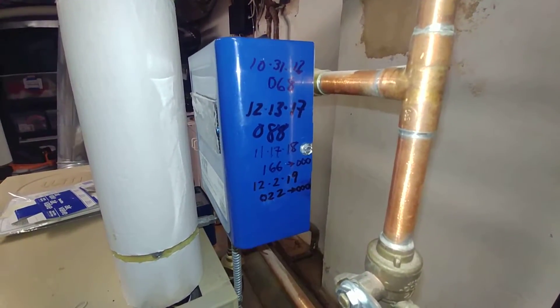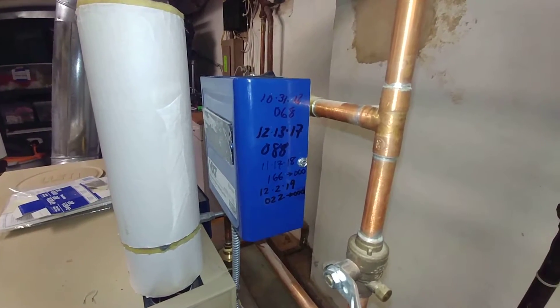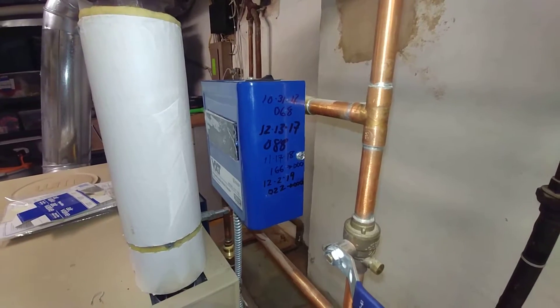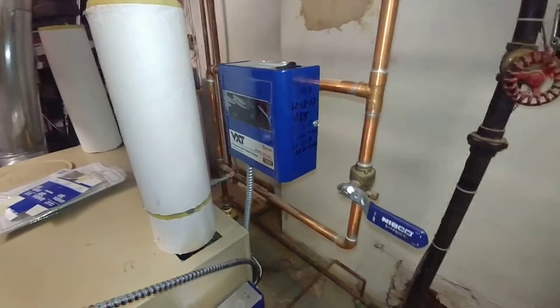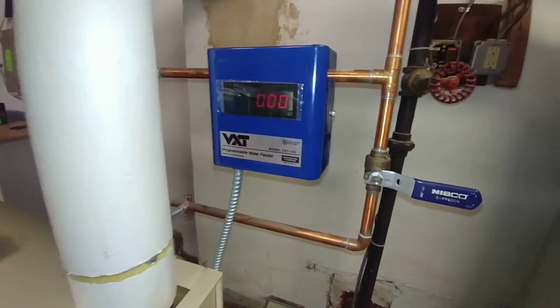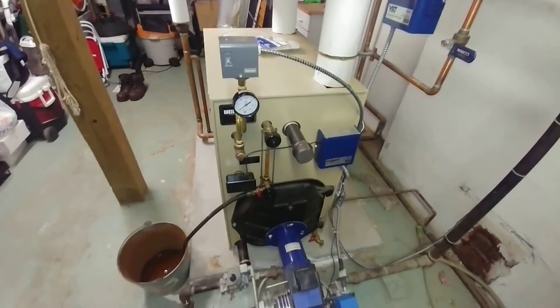It was using a fair amount of water at first until we tightened up loose packing nuts, union nuts, and the always-helpful leaking air vents. Now we've reset the VXT to zero — it cycles on pressure when you run it long enough.